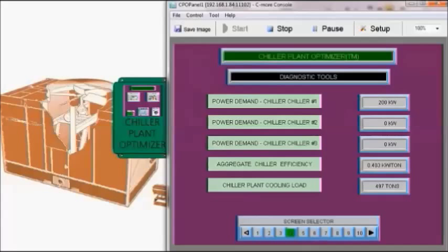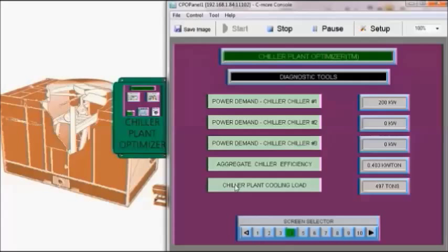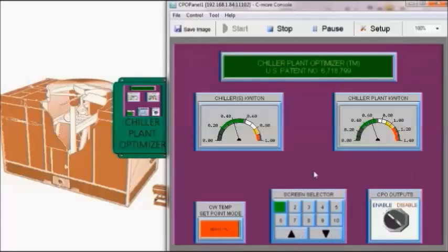Our chiller power demand has dropped to 200 kilowatts. Chiller efficiency is now 0.403 kW per ton. And we still have the cooling load of 497 tons. So now we're beginning to see what condenser water reset can really do for us. And we want to see what the total plant kW per ton is about 0.55 kW per ton.